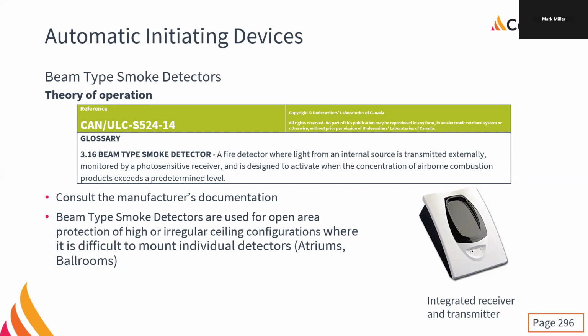We don't want to put them in direct sunlight because we're going to baffle it. We can put them in places like gymnasiums. You know, there's basketballs flying through the air all the time. That's actually not an issue. They don't react so quickly that they'll go into alarm because of a basketball going through. And if you just 100% cover the beam detector, it's not going to go into alarm. It's going to go trouble, right? Because it's smart enough to figure that out.